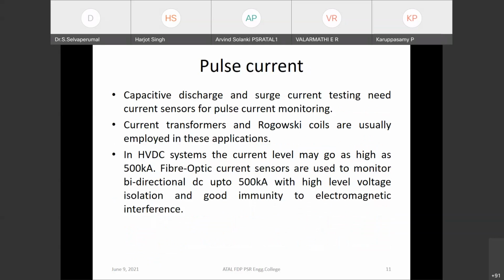So the third technique is pulse current. So capacitive discharge and surge current testing need current sensors designed for pulse current monitoring. So current transformers and Rogowski coils are usually employed in these applications. In HVDC systems, the current level may go as high as 500 kiloampere. Fiber optic current sensors are used to monitor bidirectional DC up to 500 kiloampere with high level voltage isolation and good immunity to electromagnetic interference.